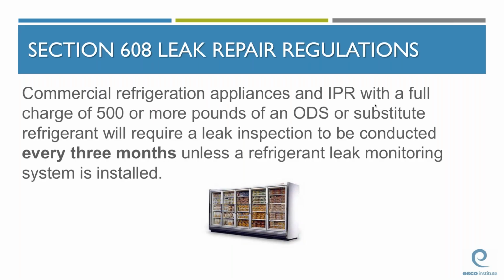As we just mentioned in our discussion of the chart, for commercial refrigeration and IPR systems that contain more than 500 pounds of refrigerant, follow-up leak inspections must be every 3 months for 1 year. That amounts to 4 follow-up leak verification tests in addition to the initial leak test that was performed when the system was first repaired. So for these systems, there'll be a minimum of 5 leak tests performed.